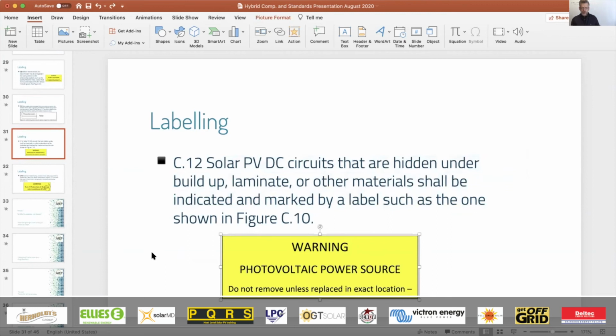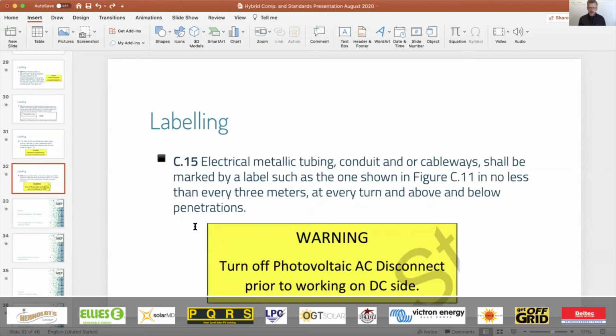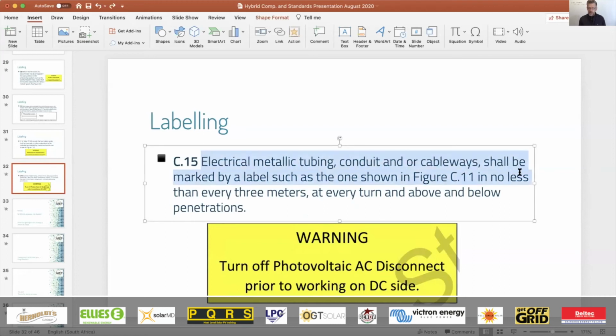So when you're running solar cables underneath a roofing sheet, for example, and you can't access it from anywhere, you're going to have a warning sticker up there indicating that you've actually got cables running underneath it. Then electrical metallic tubing, conduit, and or cableway shall be marked by a label, such as the one shown here.